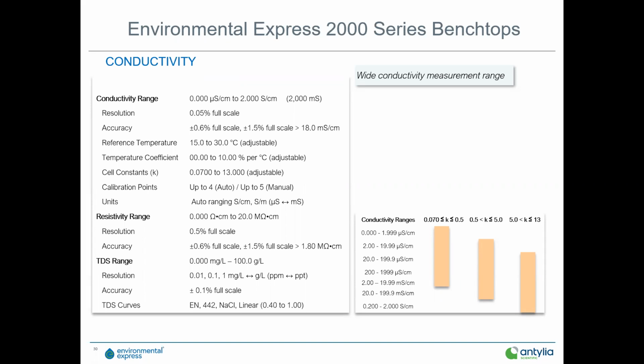The cell constant of 1.0, that's your good average everyday cell. That won't do really good at the super low end, but it will cover 85, 90% of the measurements. And then your K equals 10 cell, that's really for your seawater and super high end measurements. So 0.1, a 1.0, and a 10. Those are very common.